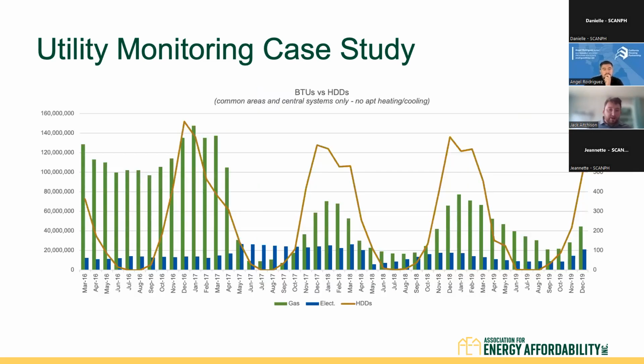So, utility monitoring case study. In this project, the gas is in green and the electricity is in blue. This is all in BTUs, so it's all apples to apples. By switching over to heat pump water heating in May of 2017, you can see the reduction in gas and the uptick in electricity. That is the effect of switching to central heat pump water heaters, and of the efficiency difference between gas and heat pump water heaters.